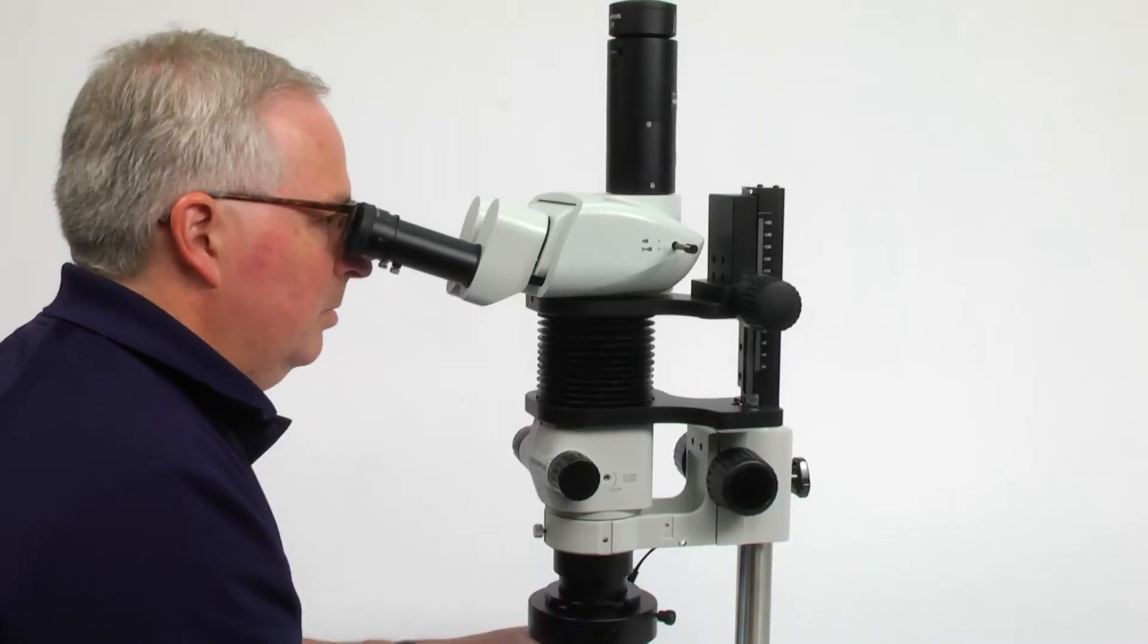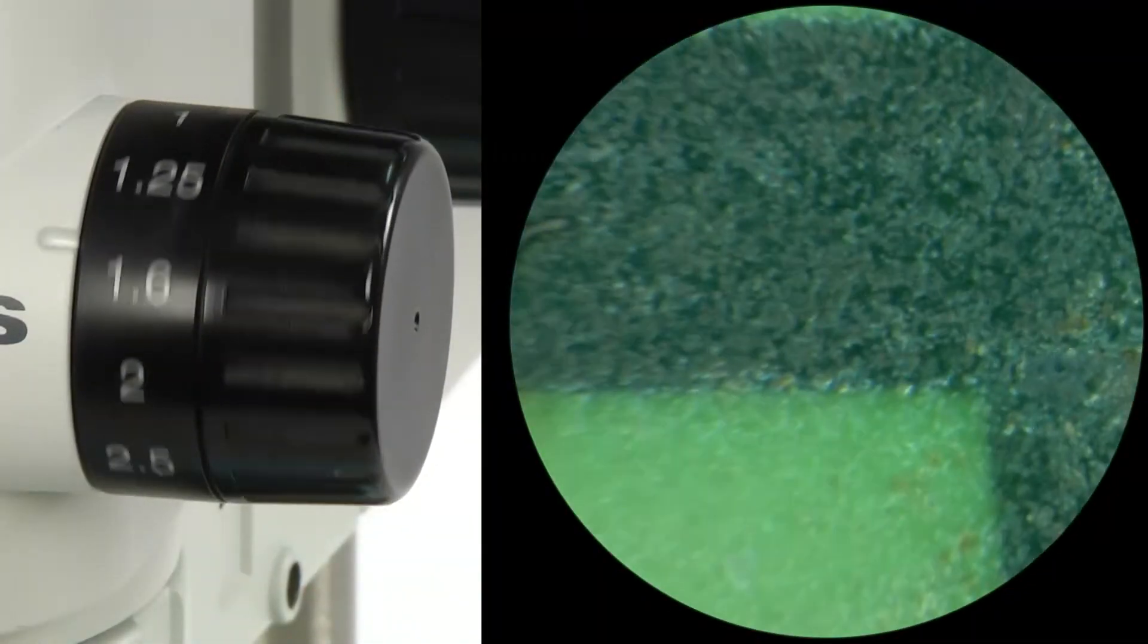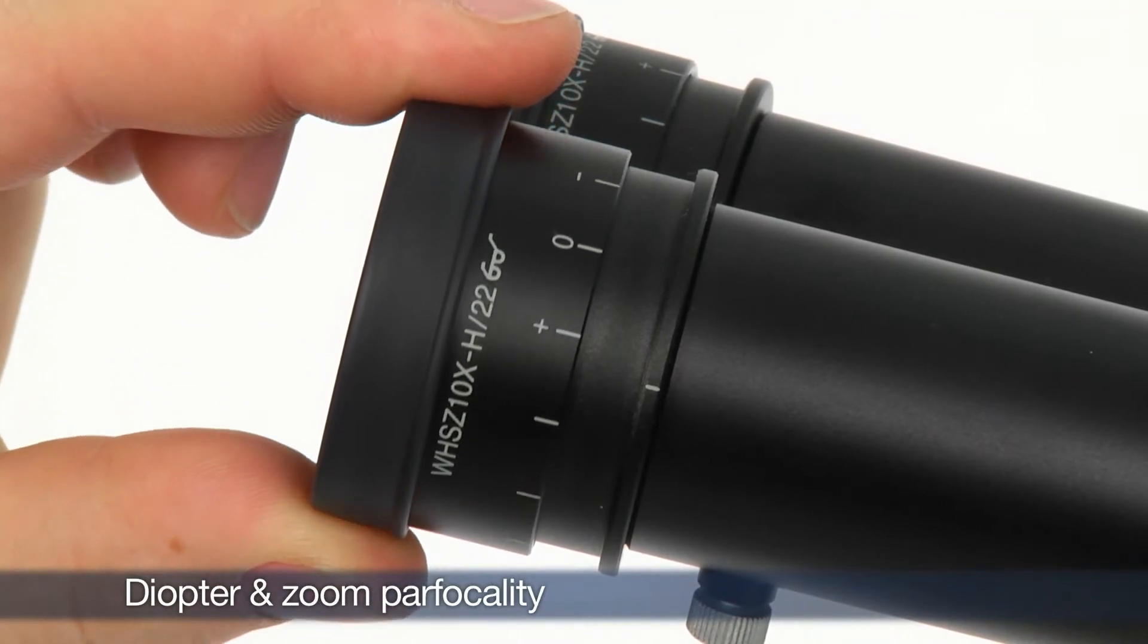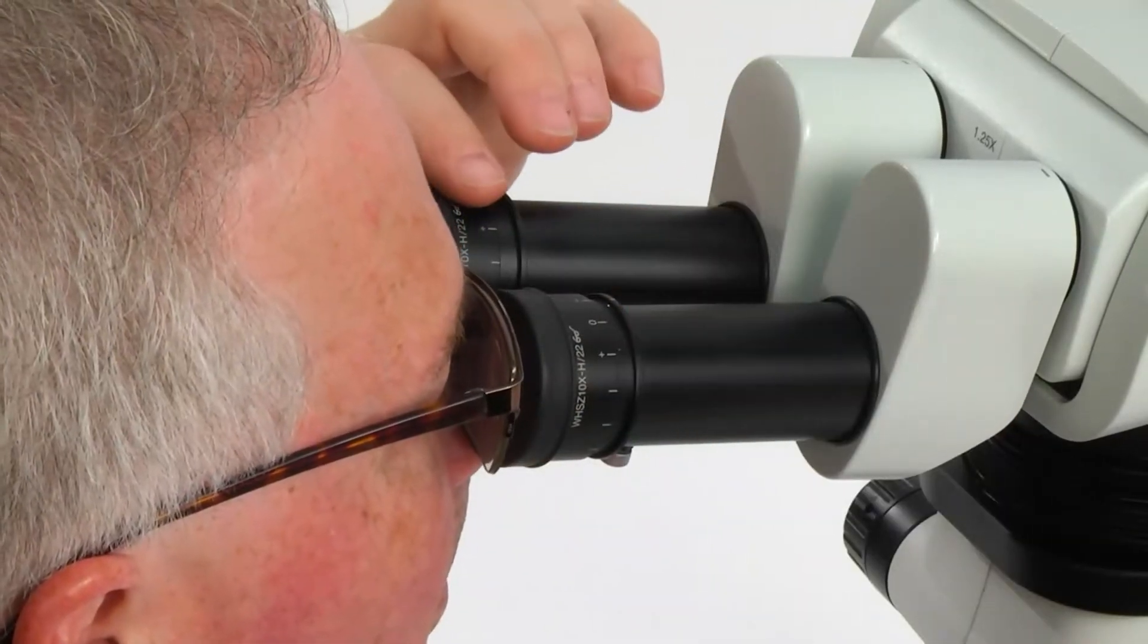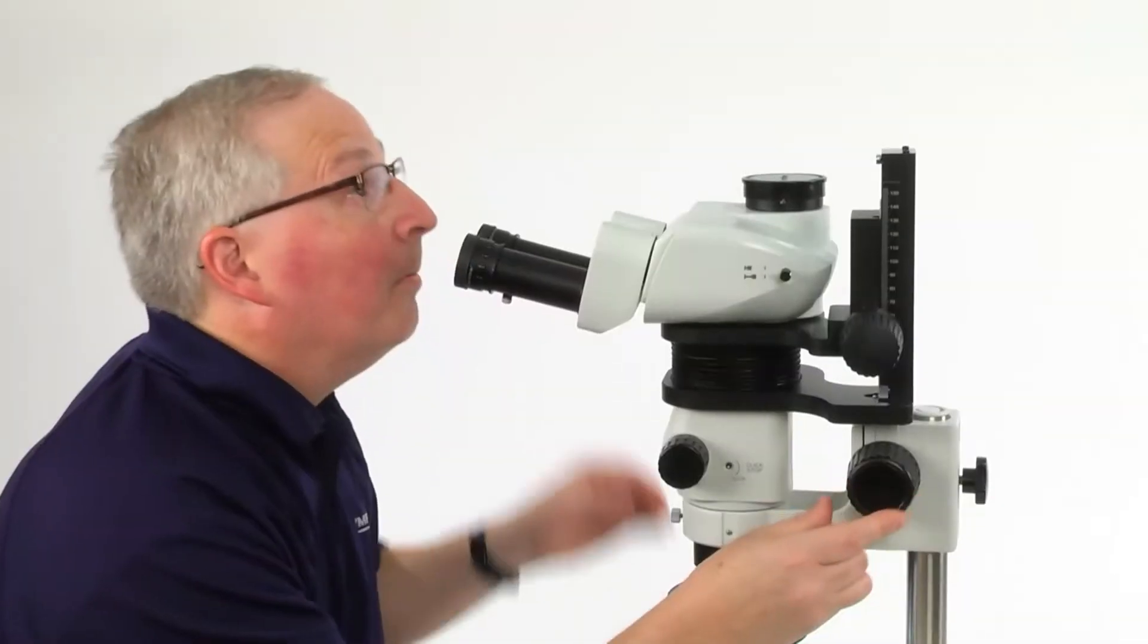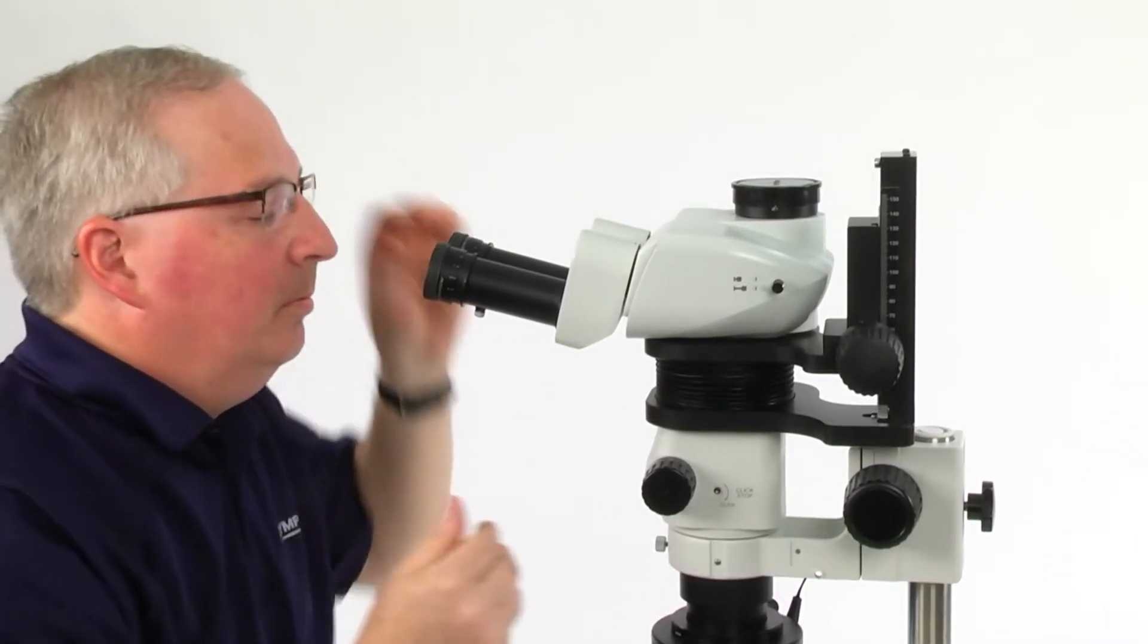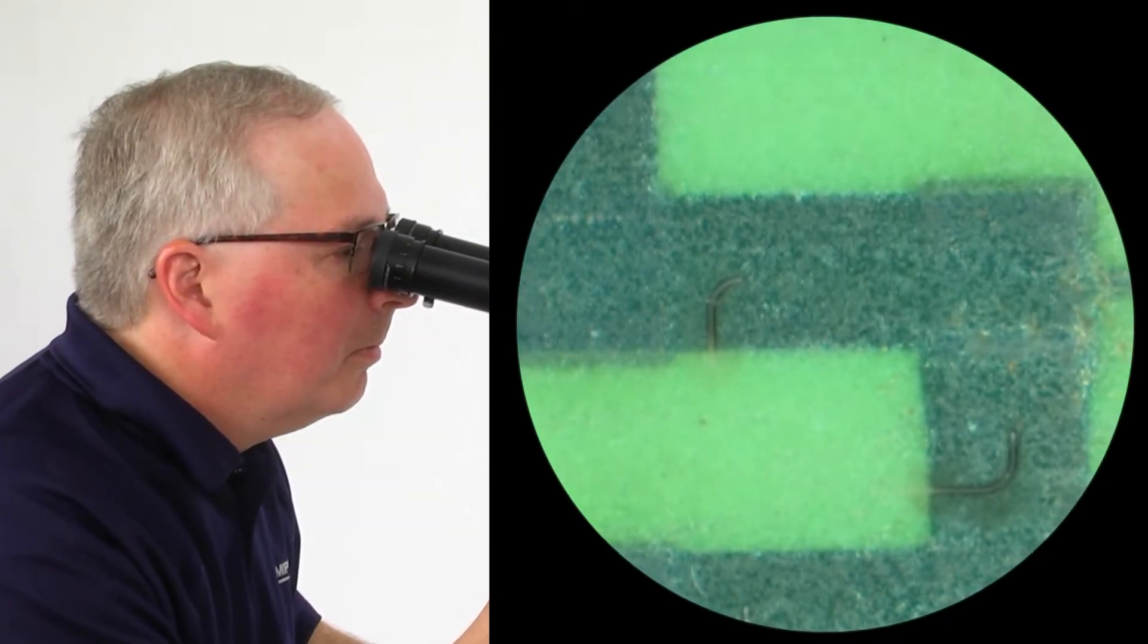Next, the stereo microscope must be properly focused to provide a clear image from low to high magnification. The diopter and zoom parfocality must be properly adjusted to provide consistently clear images through the range of magnifications. The diopter adjustment is used to compensate for differences between one's eyes and is an important step in preventing eye strain that can lead to fatigue as well as eliminating the tedious task of having to refocus the microscope every time the zoom is changed.